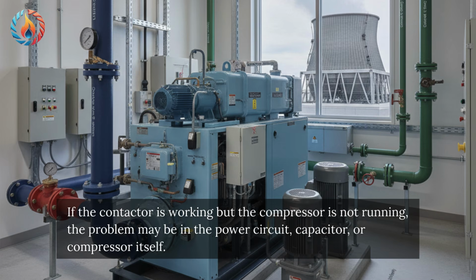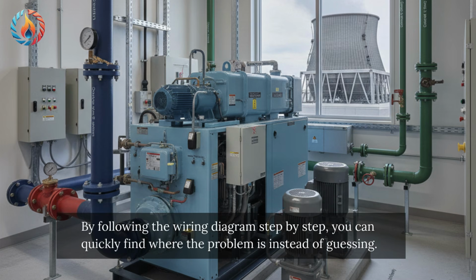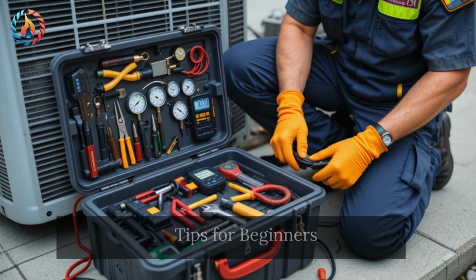If the contactor is working but the compressor is not running, the problem may be in the power circuit, capacitor, or compressor itself. By following the wiring diagram step by step, you can quickly find where the problem is instead of guessing. Tips for beginners.